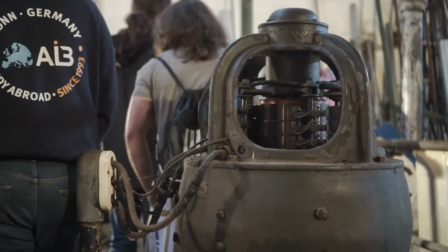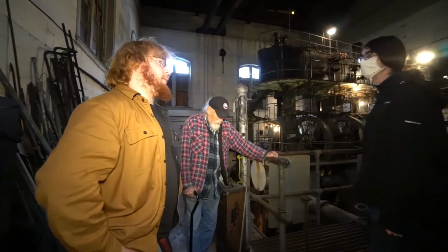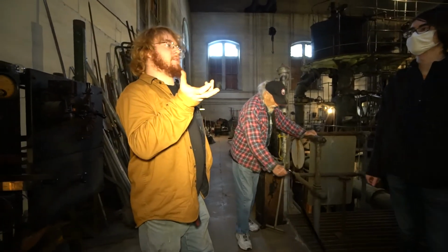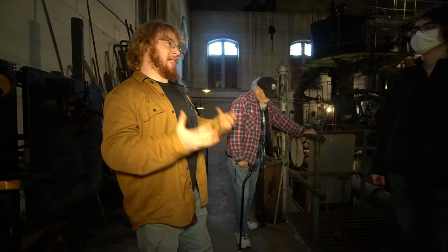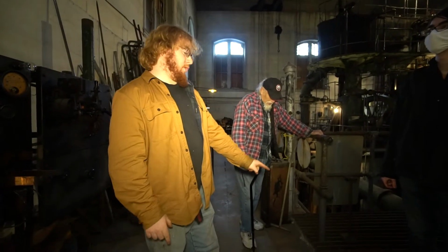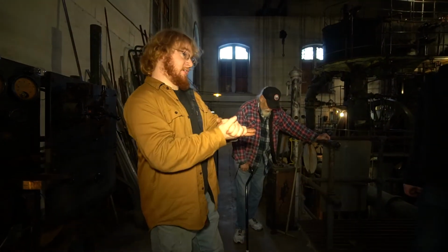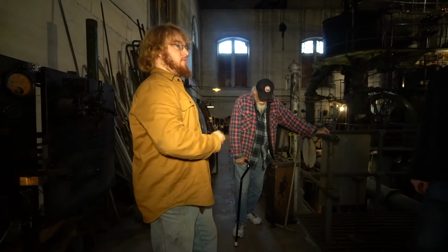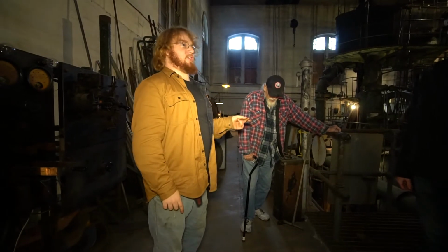What this motor is doing is, I pointed out there's a centrifugal pump all the way down at the bottom. That pump is your lift pump. The problem with centrifugal pumps is that they do not suck. They are horrible when drawing up into themselves. They will run fine when they're already primed and full of water, but they don't like it when they're not. And there's no way those two pumps, even ganged together in series, could lift water from the bottom of the pit. So they have to have another pump in the bottom of the pit that is low enough that it can start suction that pushes water all the way up to these two pumps. They go one through the next and then out to the city. So really, you have 3 pumps in series: 2 driven by a turbine, 1 driven indirectly by a turbine via an electric drive, sort of an electric transmission.